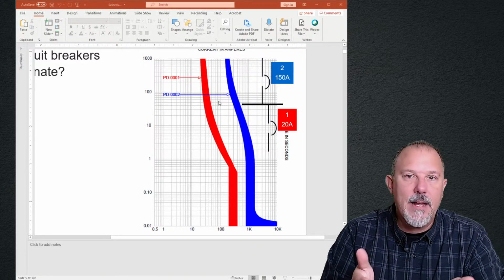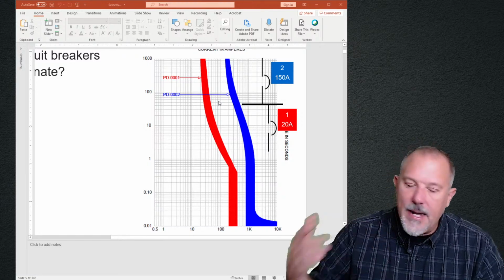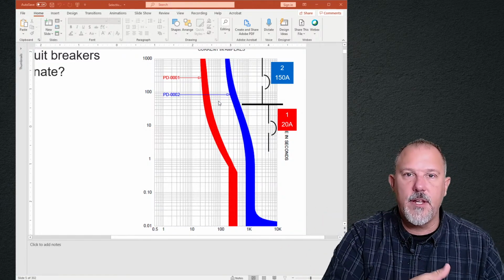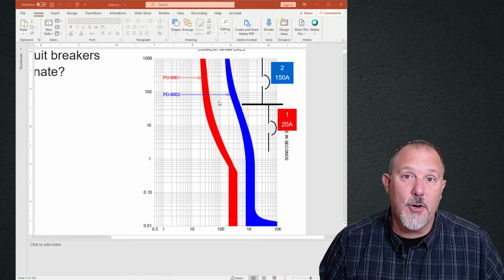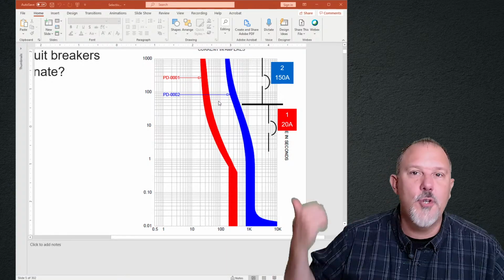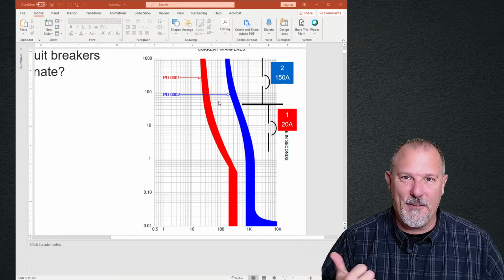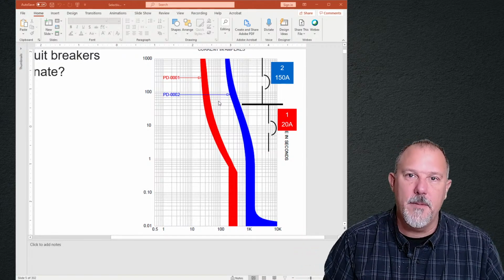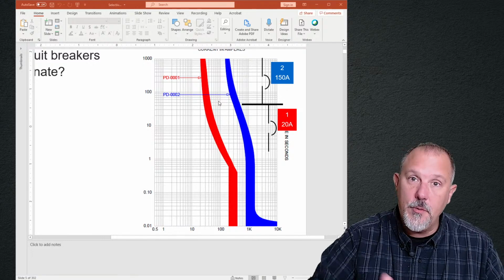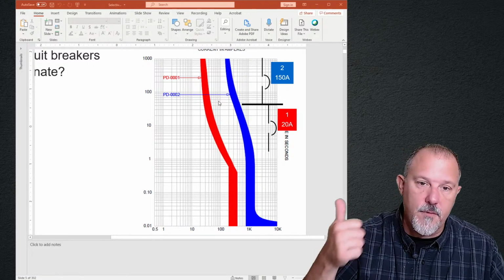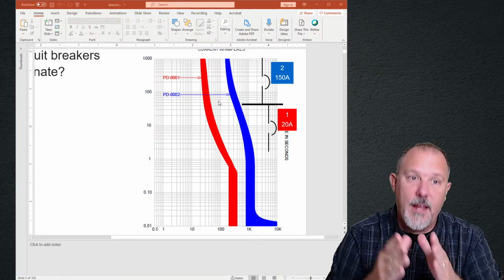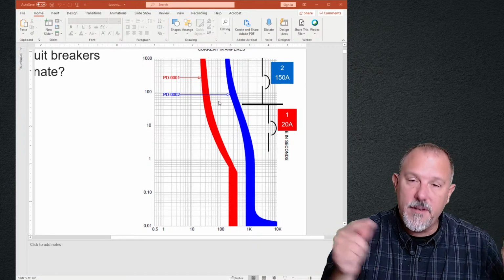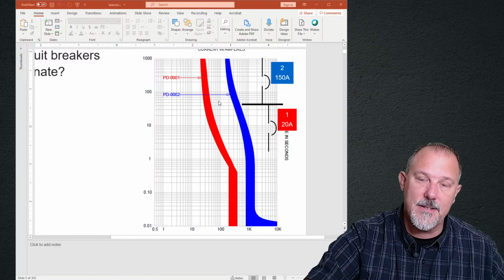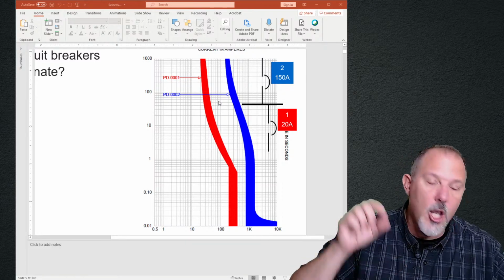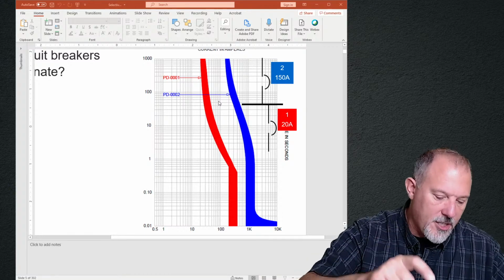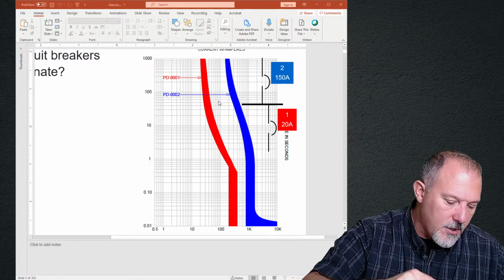So now, can I selectively coordinate? Can I buy a series rated system and still selectively coordinate? Well, sure, if your fault currents are low enough, but you don't need to series rate it, because if they're low enough, then you will interrupt them. But if they're high enough that you need to series rate, that means both of those devices are going to open to clear the fault together. And that is counterproductive to the very first portion of that sentence, because you will not be localizing the overcurrent condition to restrict the outages just to the circuit or equipment affected.